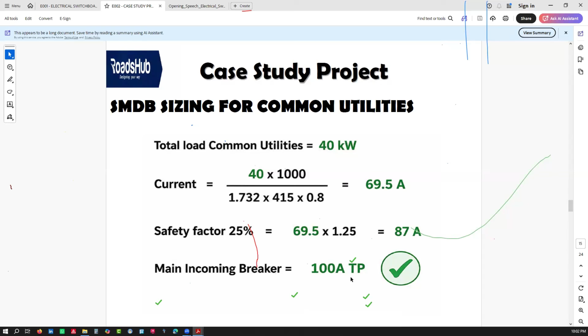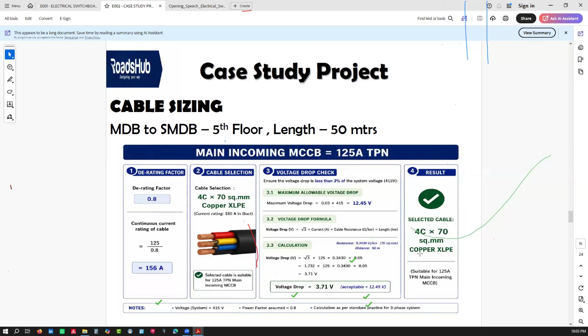And we have calculated the total main breaker that we need. And then you need to also do the cable sizing from the SMDB to the MDB. You need to do the size of those cables. And that's exactly what we did here. And we got that we need a four-core 70 mm squared copper XLPE because we used a 125. So you see this 125, we divided by the derating factor, and then we went into the table, and then we got the cable size, we tested for voltage drop, and then we selected that cable. That's the actual process. That's the correct process for you to be able to do that selection.